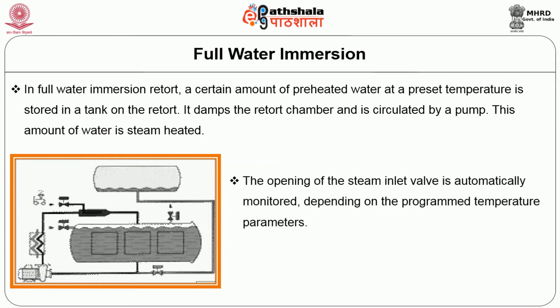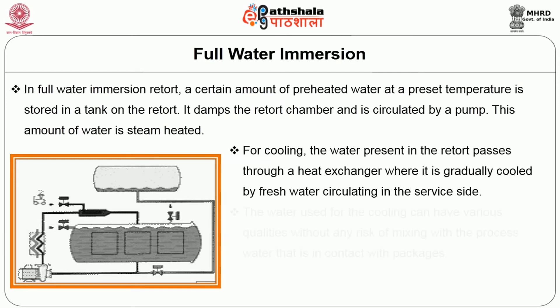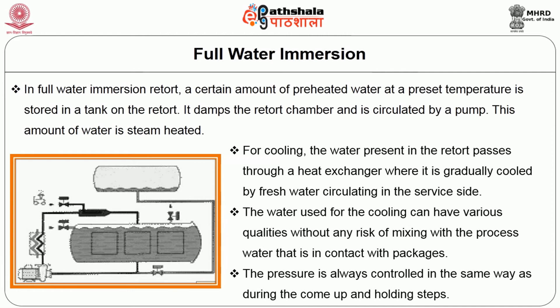Full water immersion retort: In a full water immersion retort, a certain amount of preheated water at a preset temperature is stored in a tank on the retort. It floods the retort chamber and is circulated by a pump. This water is steam heated, with the steam inlet valve automatically monitored based on programmed temperature parameters. Pressure is independently controlled from temperature by injecting or venting compressed air. For cooling, the water in the retort passes through a heat exchanger where it is gradually cooled by fresh water circulating in the service side, allowing various water qualities to be used without any risk of mixing with the process water in contact with packages.